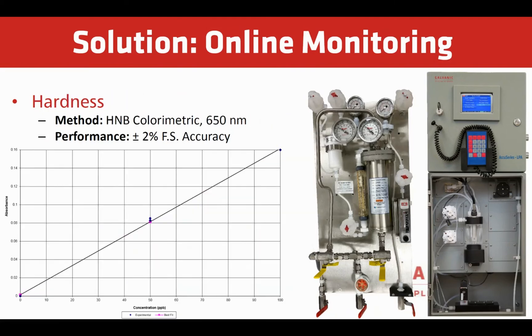Accuseries can also monitor hardness down to two parts per billion. We use a colorimetric method with a performance of plus or minus 2% of full scale. This level of sensitivity monitors slow increases of hardness that can damage the electrolyzer. Galvanic's wet chemistry analyzers have been monitoring brine for over 30 years, and the robust fluidic system minimizes maintenance to ensure continuous real-time monitoring.